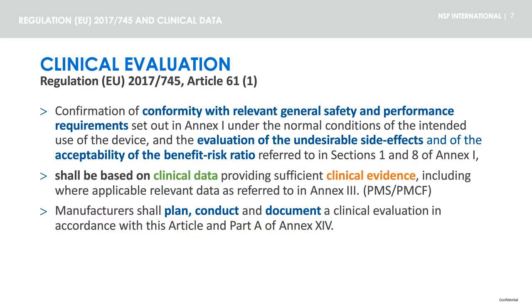Article 61 of the regulation defines clinical evaluation. The aims of the clinical evaluation are to confirm the conformity of a medical device with relevant general safety and performance requirements, as well as to evaluate the undesirable side effects and the acceptability of the benefit-risk ratio. A clinical evaluation has to be based on clinical data, and this data should provide sufficient clinical evidence, including, where applicable, data from the post-market surveillance and post-market clinical follow-up.